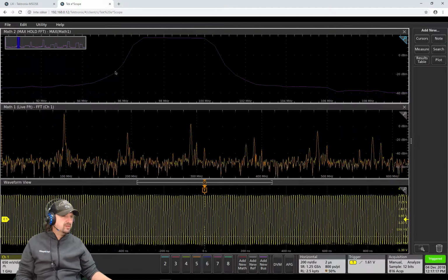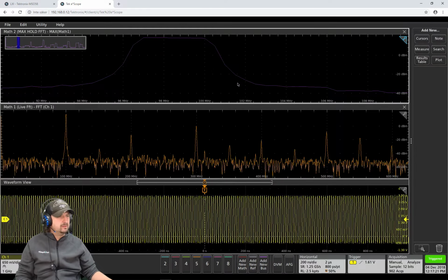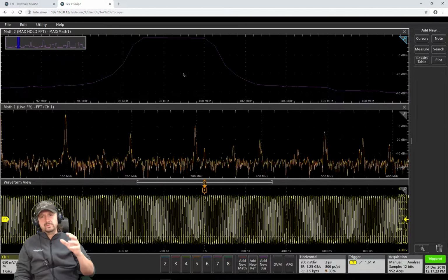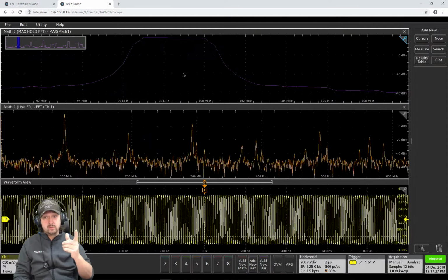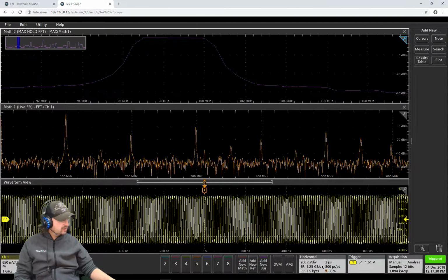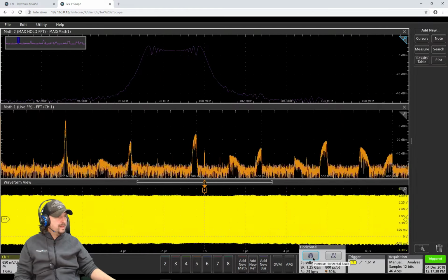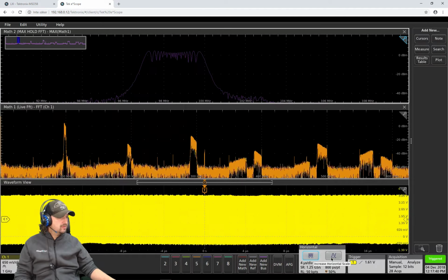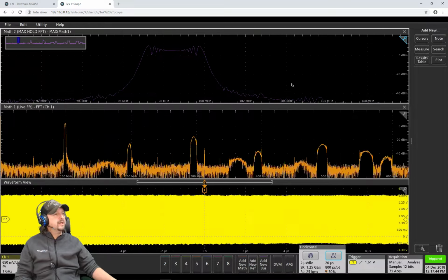One of the things you can see is that it's hard for me to do any very good measurement because the number of points I have is low. So, as with a normal spectrum analyzer, I need to add resolution. Resolution equals time, so I go down here and add some more time to it. Every time I do the FFT, it takes time to do the max hold, but at one point I will not see that much difference. We keep this one.